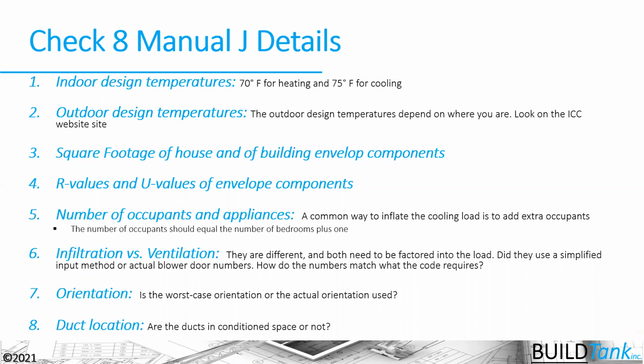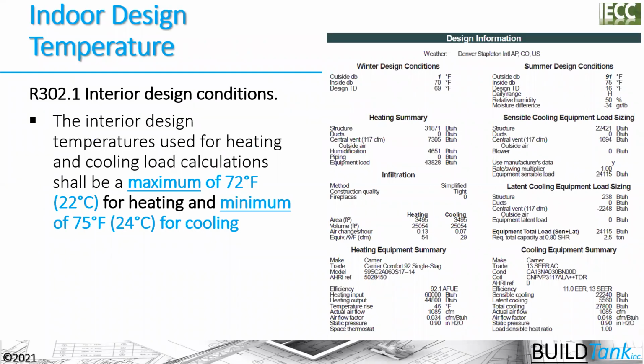So let's start by looking at the indoor design temperature. The indoor design temperature is governed by the IECC. The IECC says that the heating and cooling loads calculation shall be a maximum of 72 degrees for heating and a minimum of 75 degrees for cooling. We can look at the design information reports that come out of the software that is used to calculate the Manual J, and we can pretty quickly see, are they using the right numbers or are they manipulating those numbers?